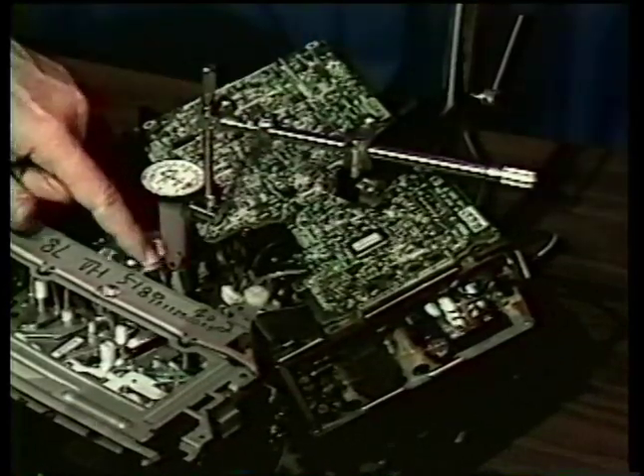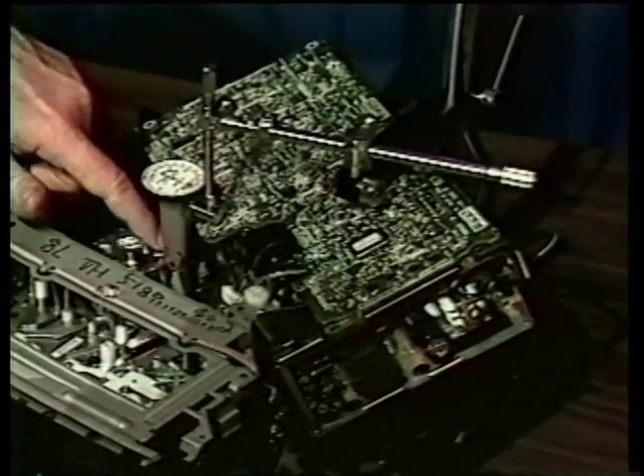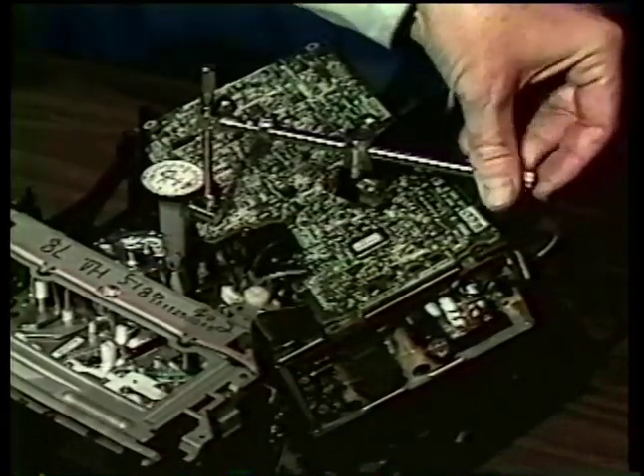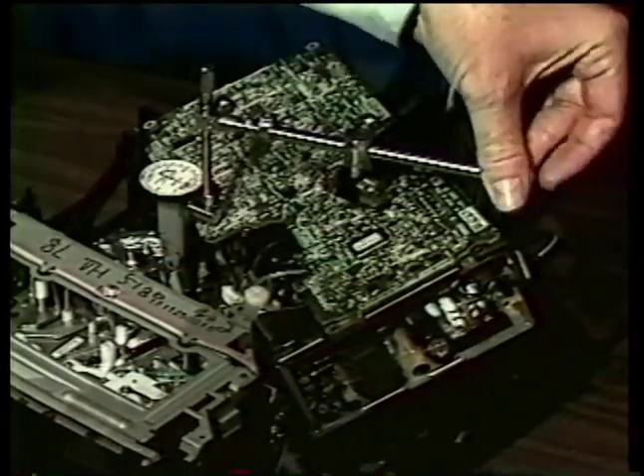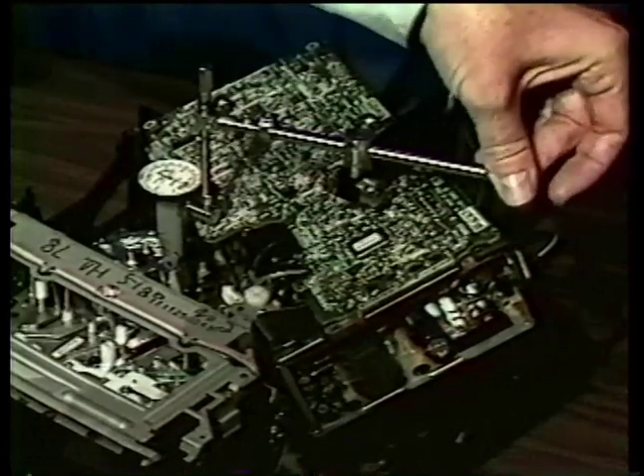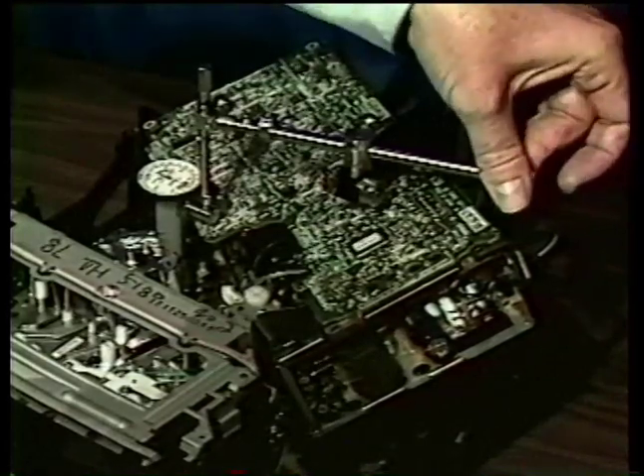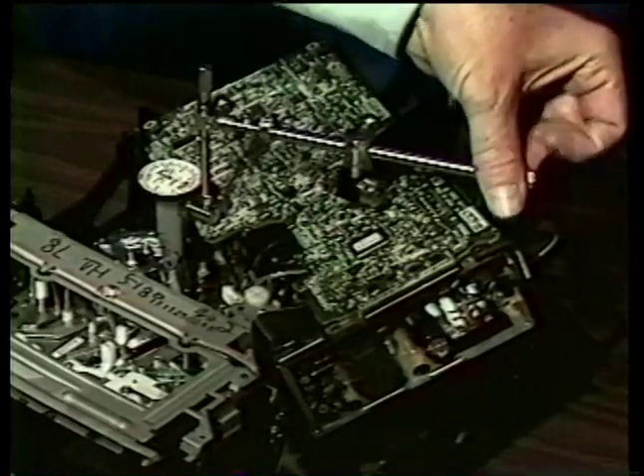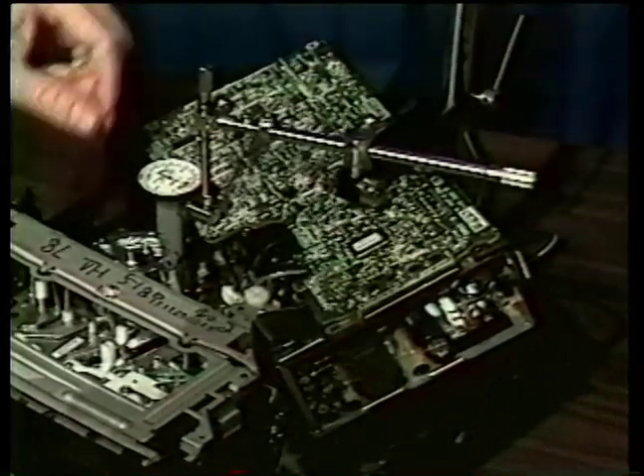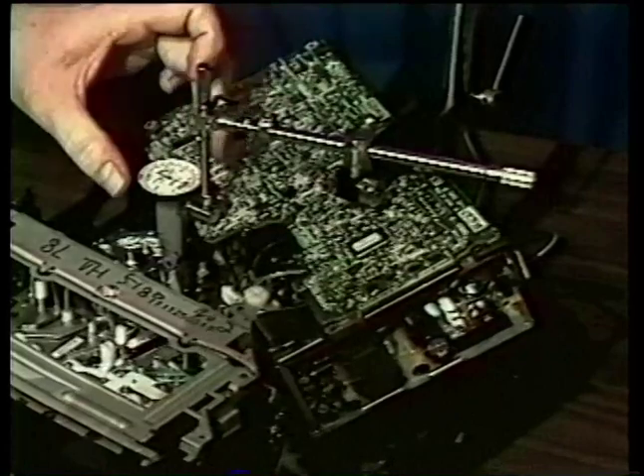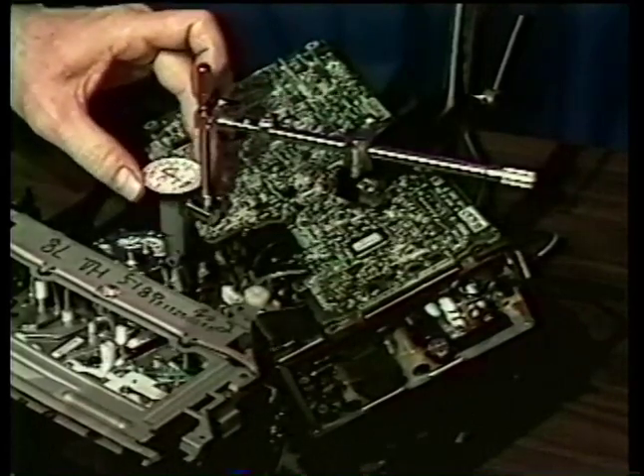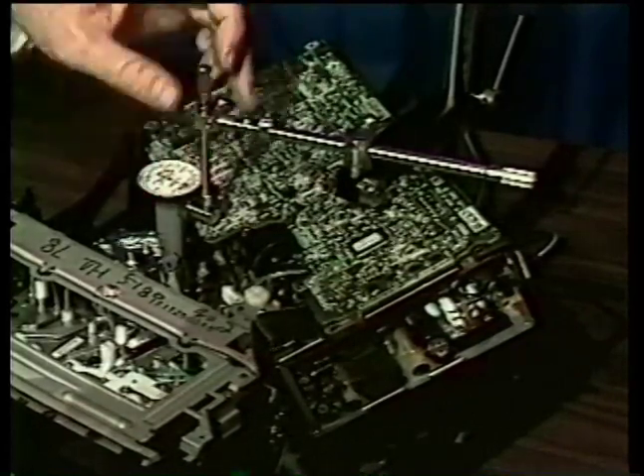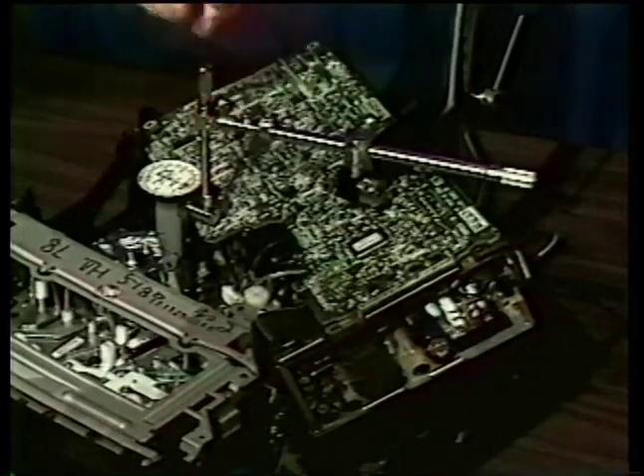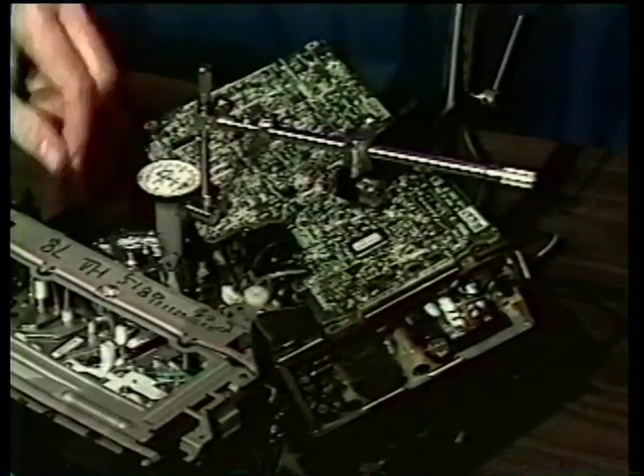I'm rotating any head tips out of the way so that as I come in I don't cause an accident. I'm using the micrometer adjustment to engage the tip against the drum. At this point, it's a good idea to look down in and see if the tip is in fact perpendicular to the drum. If it's not, do kind of a tweaking operation with this so that the tip is in fact perpendicular to the drum at the tip area there.